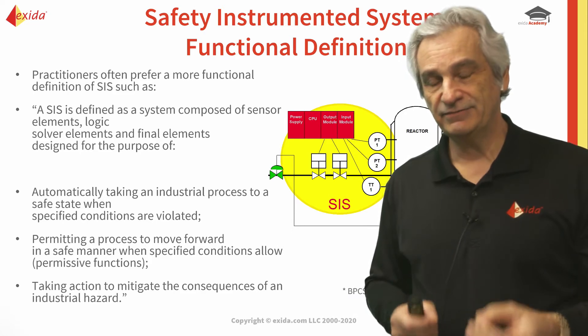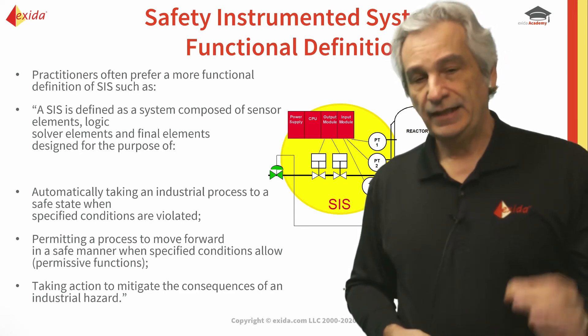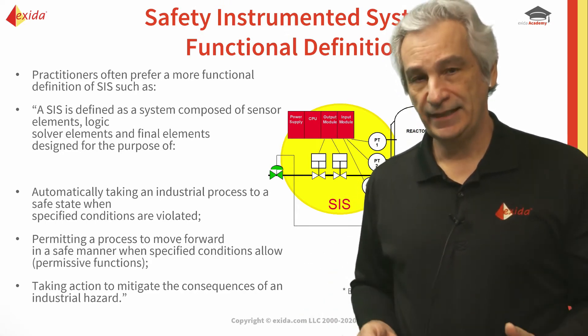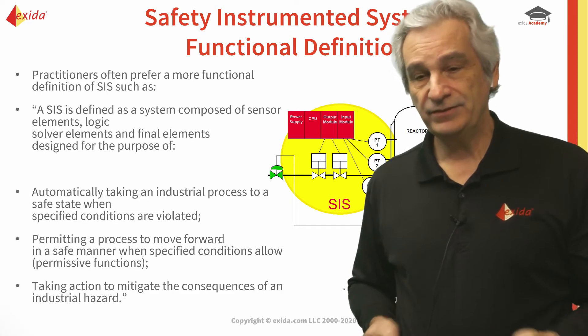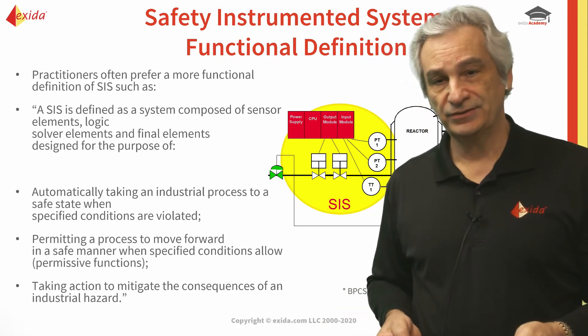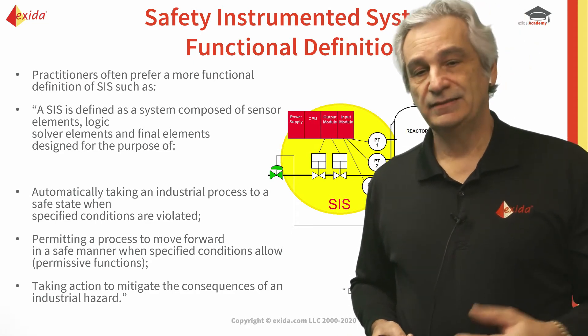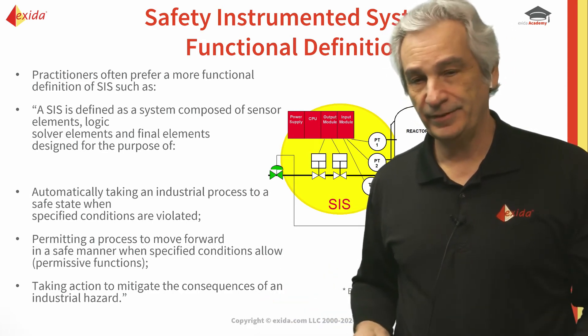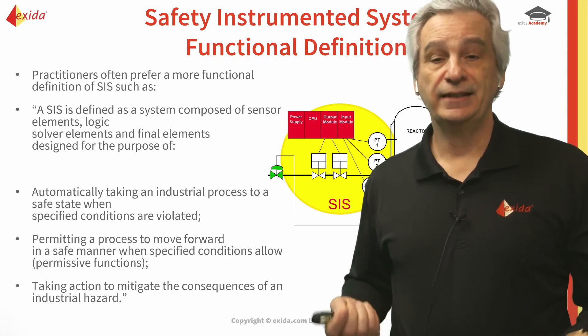People have often asked me whether a fire and gas system is a safety system — to me it is. If there is a loss of containment or a gas leak, we need to detect it as soon as possible, especially if it's highly toxic or explosive, so that a large enough concentration isn't released to find an ignition source. Back in the 1980s, gas detectors were not very reliable — part of the problem with Piper Alpha was that many gas detectors were in override or inhibit because they were giving problems. Nowadays reliability is much better and you can get certified gas detectors.